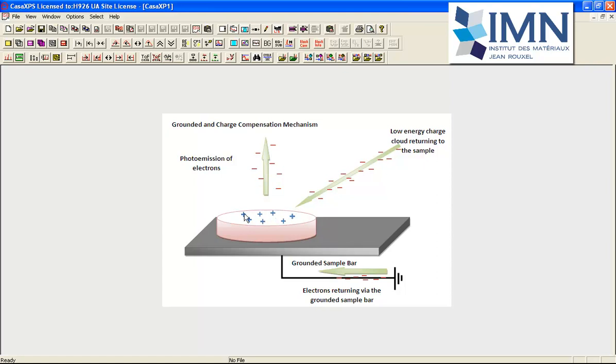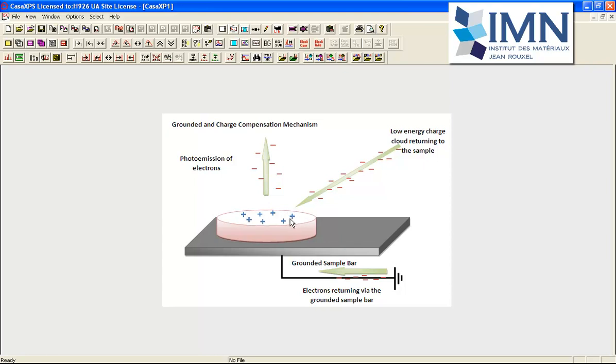The other aspect of charge compensation is that we would like a stable state. It doesn't necessarily have to be a neutral state, but what it does have to be is a state where the charge remains constant. If we have any variation in charge as a function of time, even if it is a small oscillation, this will produce a broadening of the photoemission peaks so we lose energy resolution.